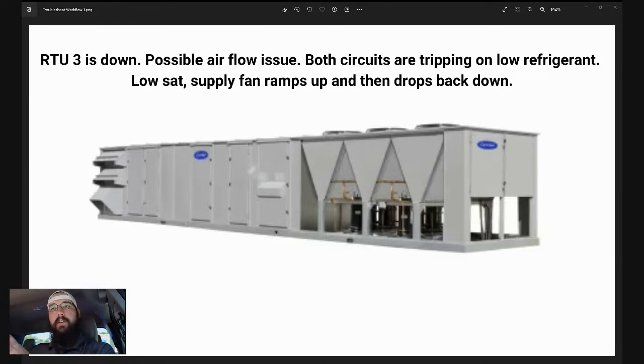But nowhere in that process is there anything that tells the fan, hey, my compressor turned on, turn the fan off. So that should be an indicator to you that it's probably not even a logic issue in the controller, but it becomes a relay logic issue. That's just a fancy way to say that we've probably got a contactor or a relay, something control-wise, not functioning properly. So the first thing I would want to do in a situation like that is go straight to the output relay that controls the supply fan and sends our start signal, in this case, to the drive. And I'd want to verify, when that fan turns off, does that signal actually drop out completely?